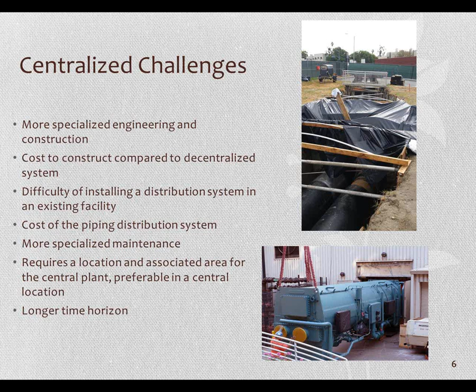How about decentralized? What are some of the decentralized benefits? Well, I think one thing is that it tends to be more robust, less prone to failure. So you can imagine if you have chillers in every building and one chiller fails, you've only lost that building. Now, how about if there's some catastrophic occurrence at your central plant - it gets hit by a meteor, for example, or something more realistic like the power feed goes out. Then you've lost your whole central plant, and now you've lost cooling to all your buildings.